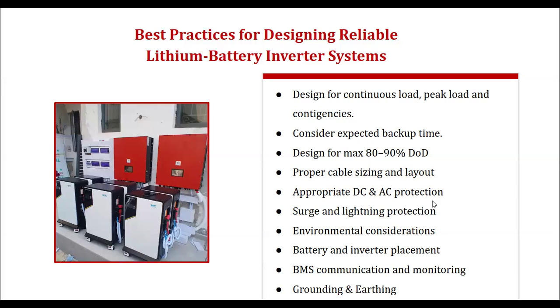Battery and inverter placement - like I said, look at the position where you want to put them so it's convenient for your customer to see what is going on with the inverter. If you put your inverter on top of a wardrobe or under decking, it's difficult for the customer to see the screen. That's why most inverters are designed to be installed at eye level, so your customer can stand in front of it and tell you what they're seeing - or if it's online, they can check performance through their phone.